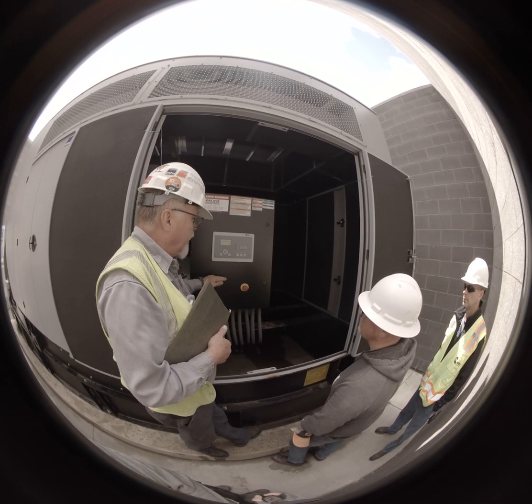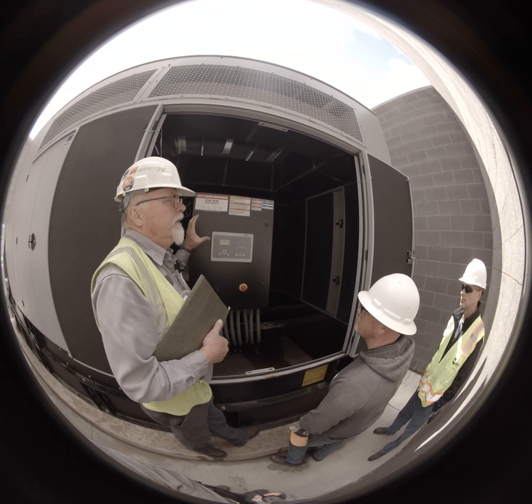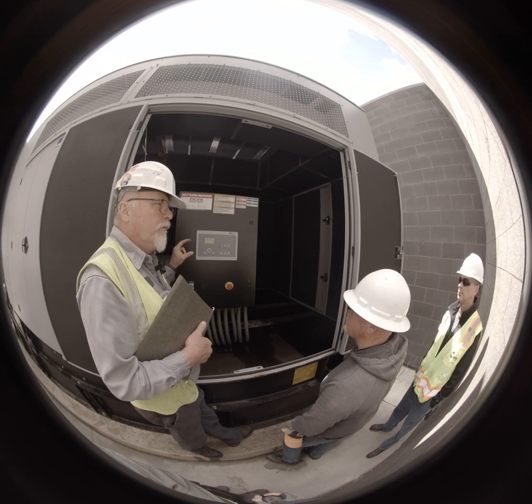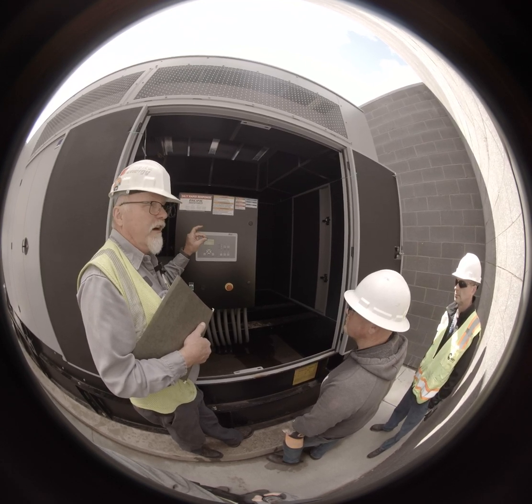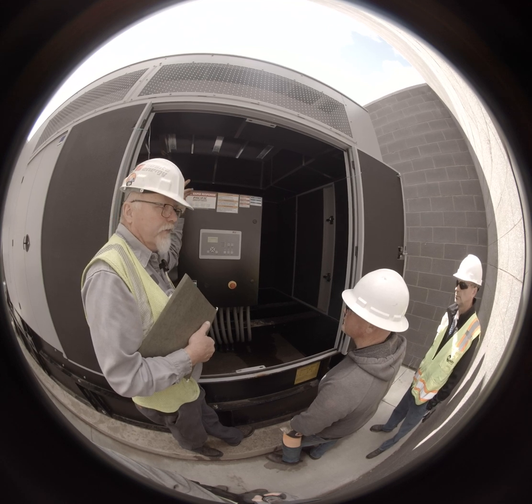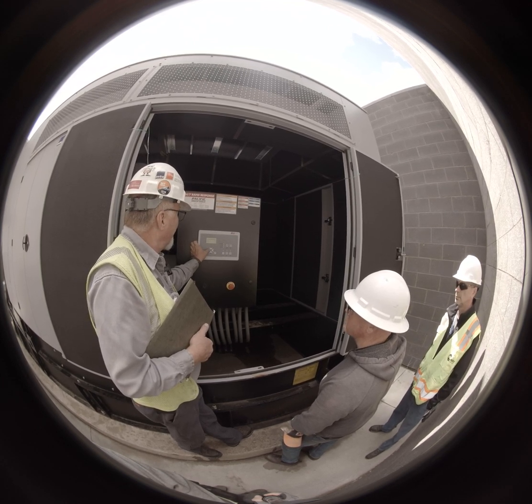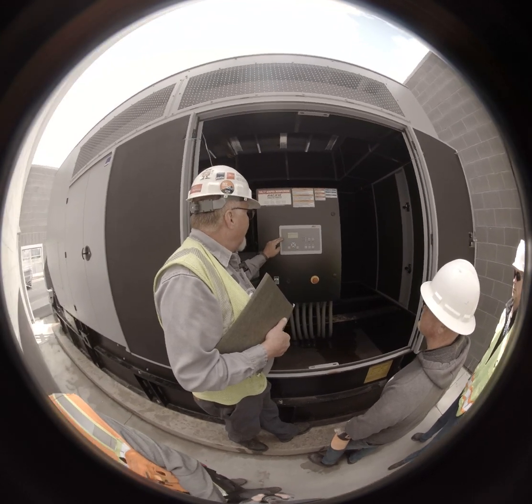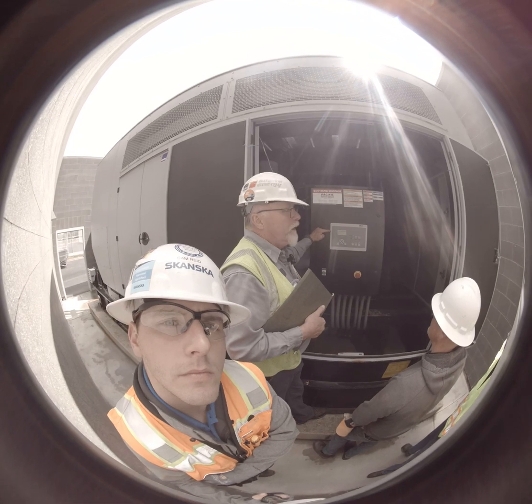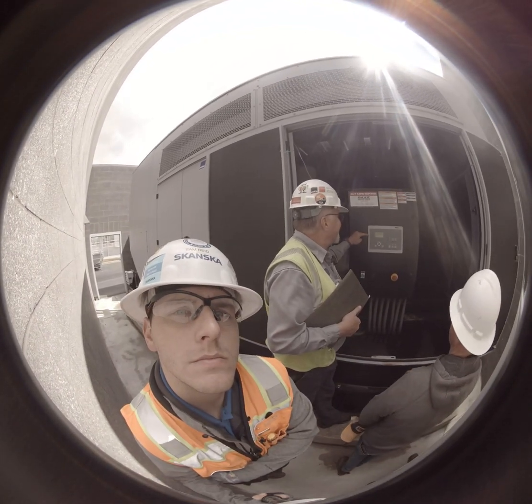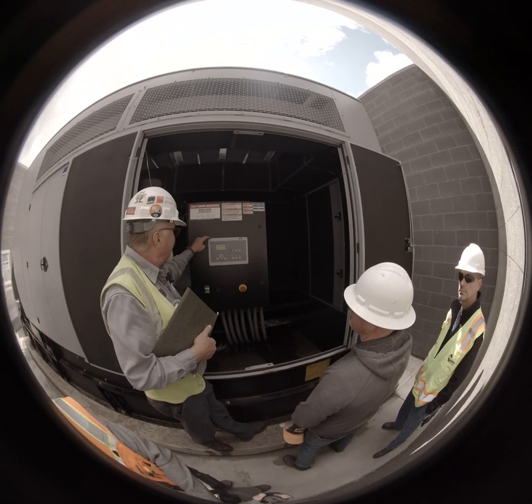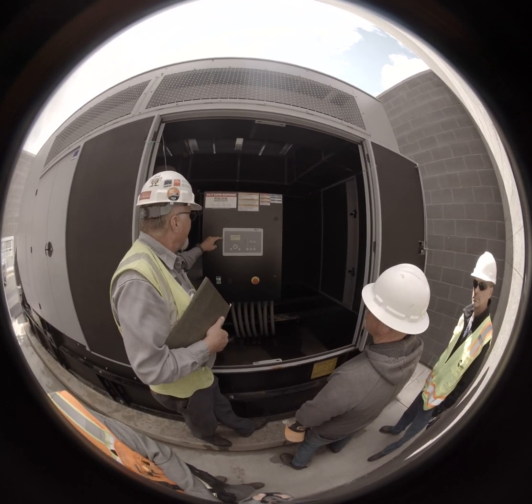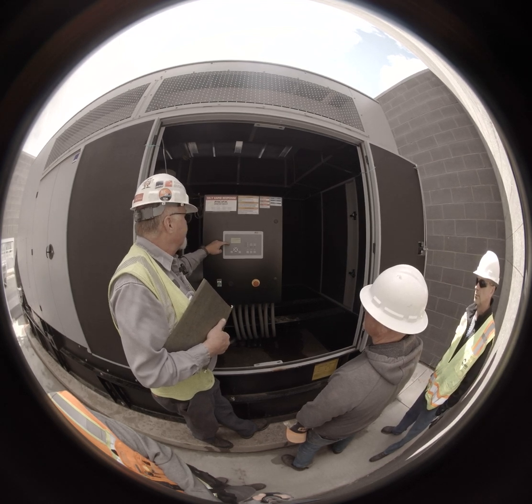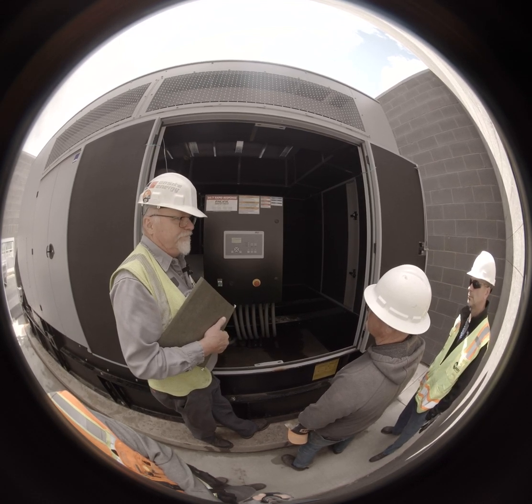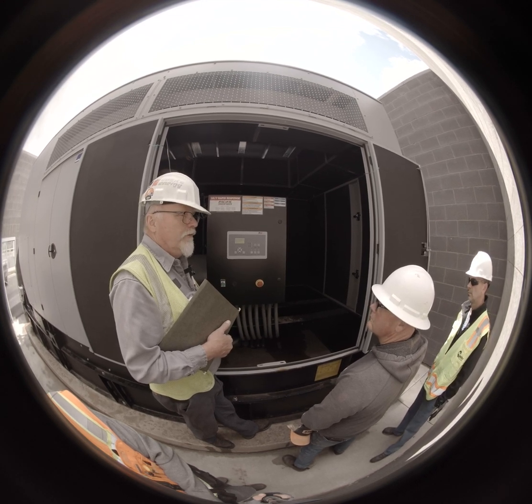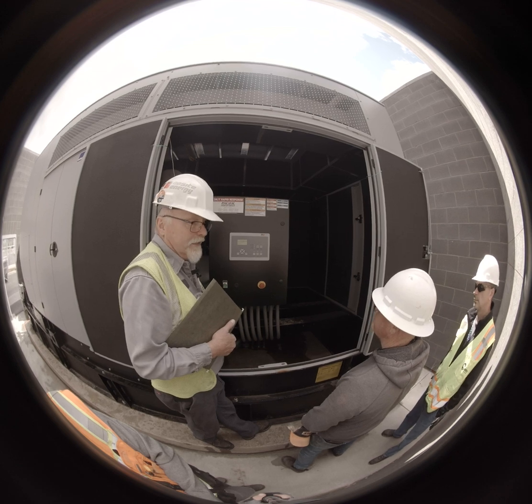Then your global alarms, and this has onboard relays that can be monitored. So basically, you can tie into that relay, and when it closes the contact, it can turn a strobe light on top of this on. You know, things like that. And then we get down into logic control relays. That's if you're writing logic. That's when you use this for paralleling and, you know, very custom stuff. Configure elements, configure protection. You can actually set it up so that if you get over 50 kW load on it, then you can have it do something.